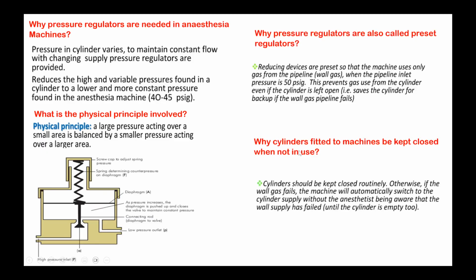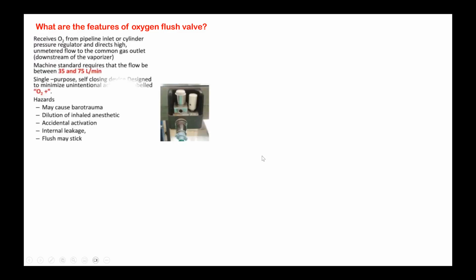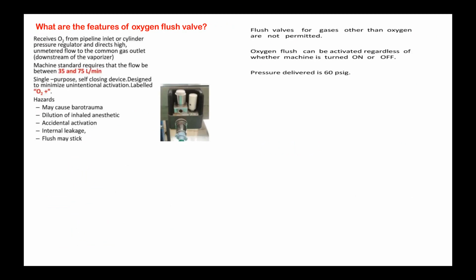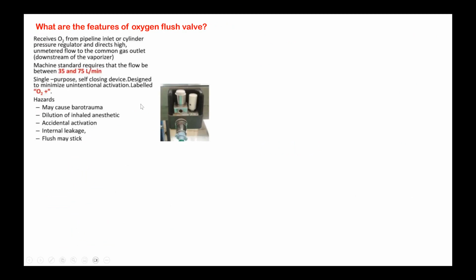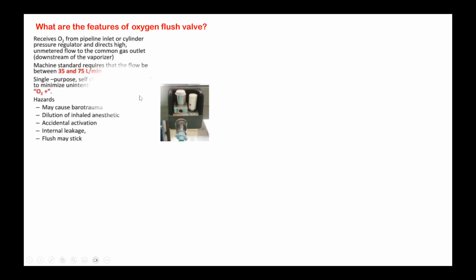Why cylinders should be kept closed. Okay, all these things. Oxygen flush valve. Sometimes we may ask you how much oxygen will be delivered if you use the oxygen flush valve. 35 to 75 liters per minute. Okay, and it receives oxygen directly from the primary. It bypasses the pressure regulator.